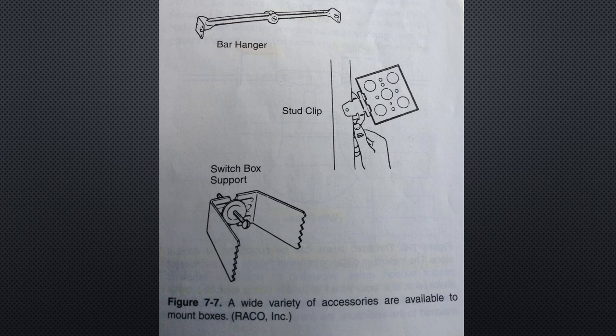Box mounting: boxes may be installed in walls, ceilings, floors, partitions, cabinets, and other surfaces. The mounting surface can be of almost any material or composition. Boxes should not be concealed or inaccessible. Boxes may be mounted directly on surfaces as long as there is adequate support. If the wall surface is concrete or wood, this is not a problem. If the surface material is inadequate, then the box must be mounted within the surface, supported by a structural member or fixed with clamps. There are a number of ways to mount a box within a wall, ceiling, or floor. Adapters and accessories are available to aid in mounting boxes. Expansion anchors, bar hangers, and mounting brackets are often used. See the figure on the screen, which illustrates some of the more common mounting devices.